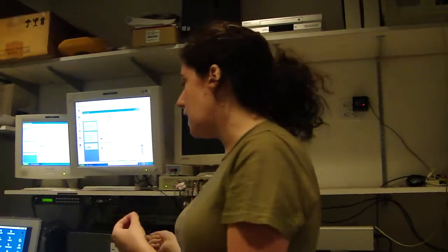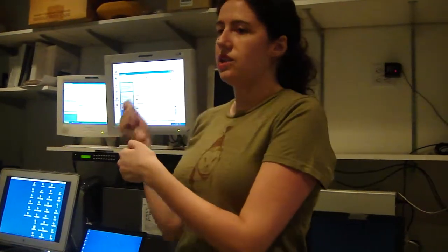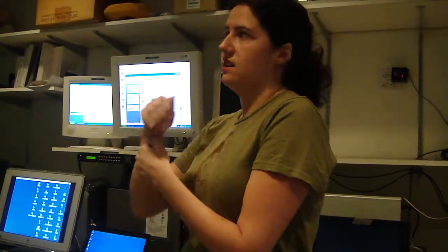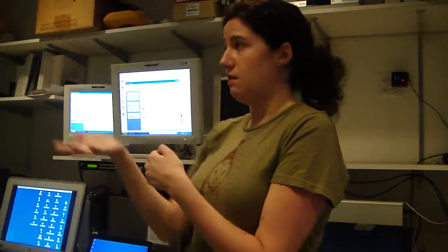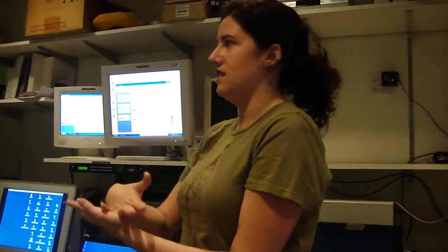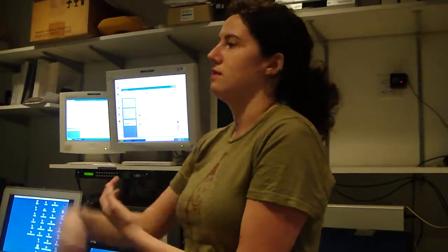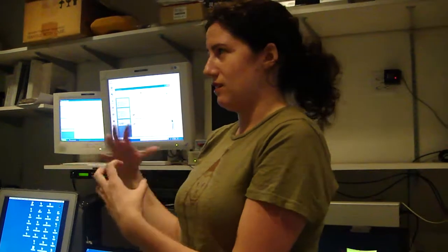When you're doing the consent and stuff, you have to let them know that occasionally there are malfunctions, and if at any point you feel a stimulus and it's too hot, which has happened, the system is set so that if there's a lapse in communication, the way it triggers its turn-off mechanism is it goes up to 53, at which point there's an automatic shut-off and the system turns off. For the subject, that is above the point that anybody can handle, and then furthermore it shuts off and goes to painfully cold.